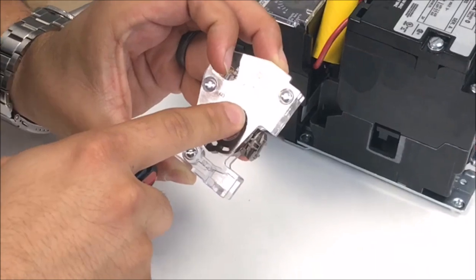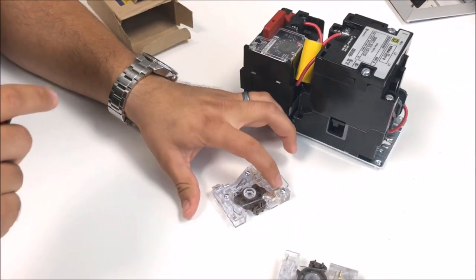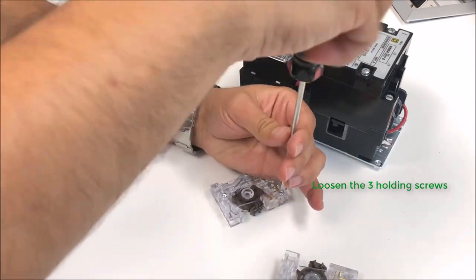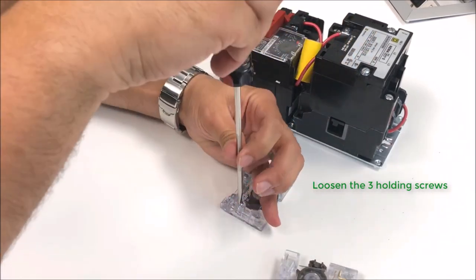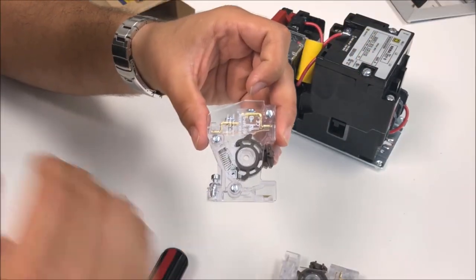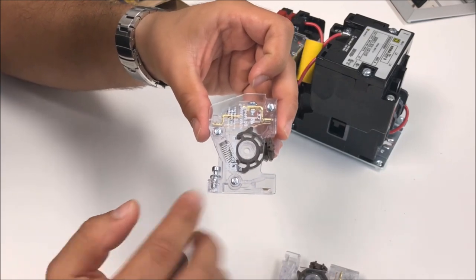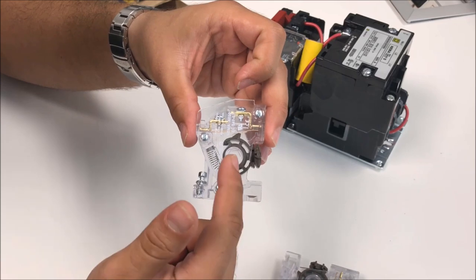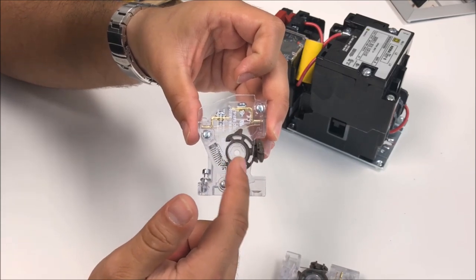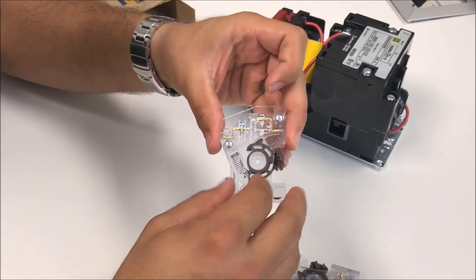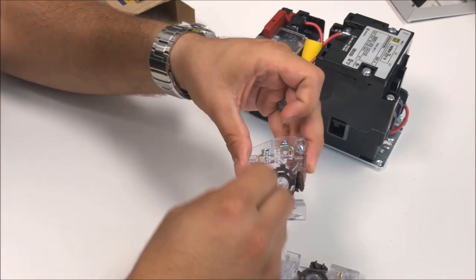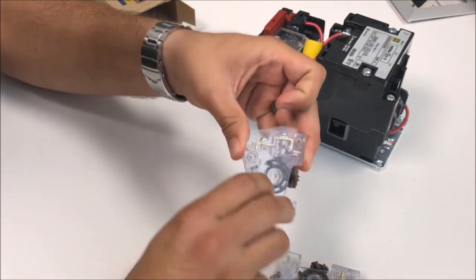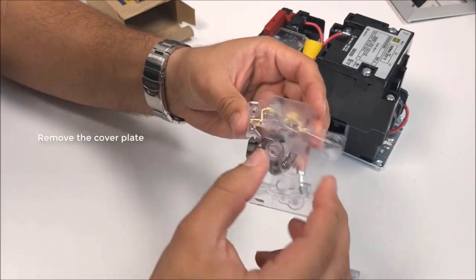We're going to convert this to a normally open. First you're going to remove the three screws holding the cover plate. Now that the screws have been loosened, we can remove the cover plate that's on the opposite side, take that cover off, and we're going to reverse the location of this cam wheel. Take the screws out, make sure not to lose them because you'll need them to put it back together. Flip it over and there's a cover plate.